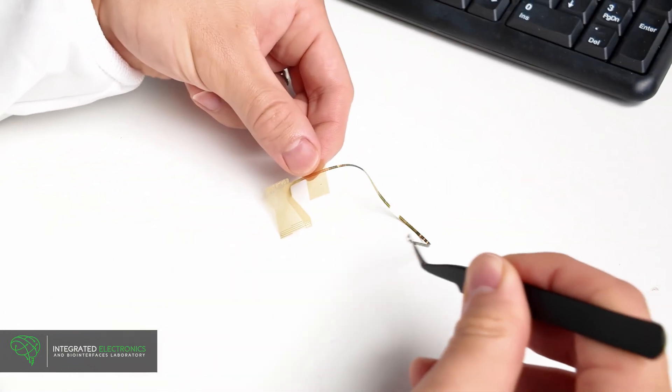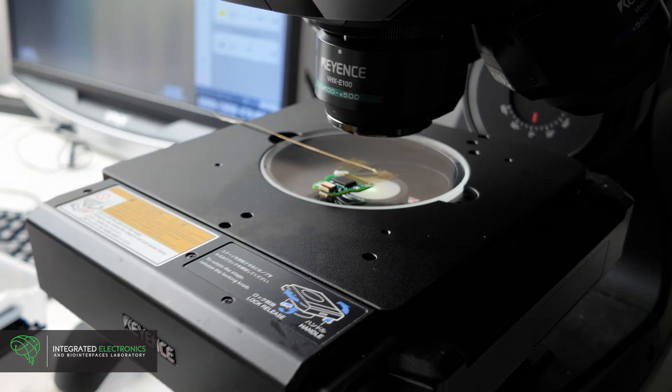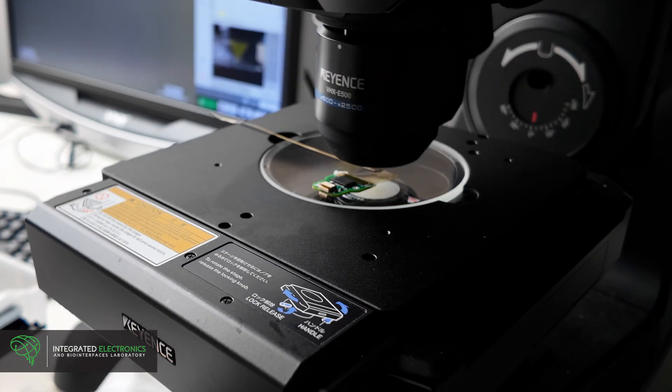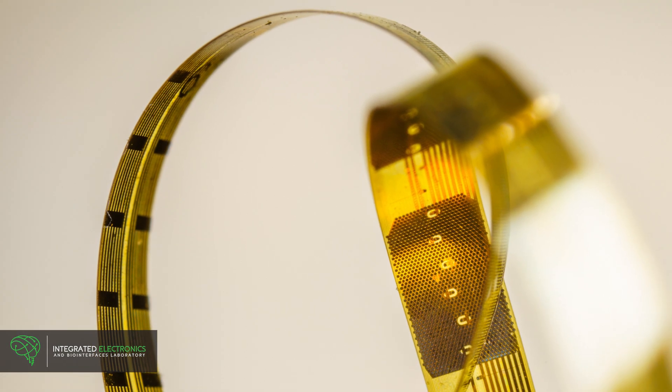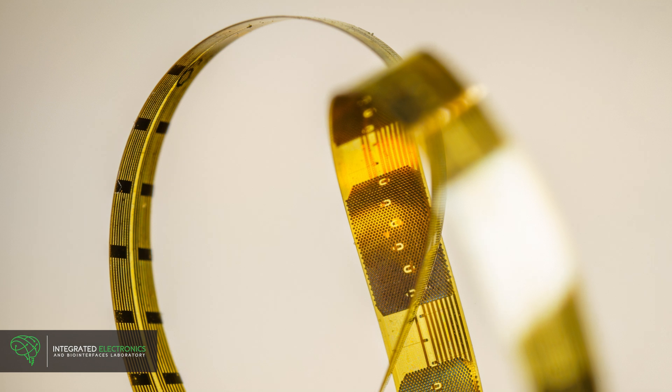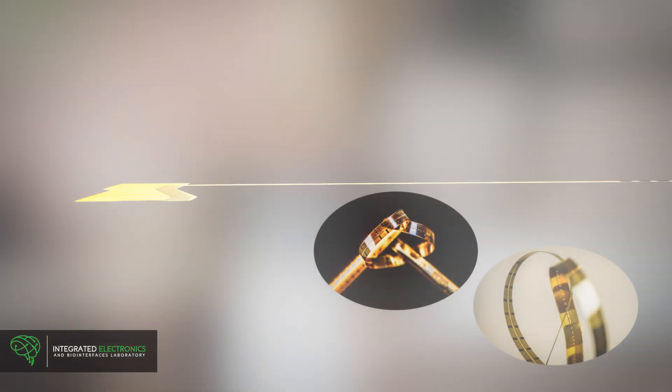It is ultra-thin and flexible, with 128 micro-electrodes that record brain activity and 16 macro-electrodes that stimulate the brain with tiny pulses of electric current. The electrode is incredibly thin, just one-fifth the width of a human hair.